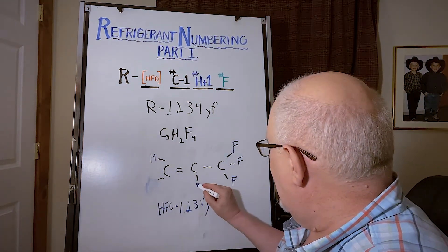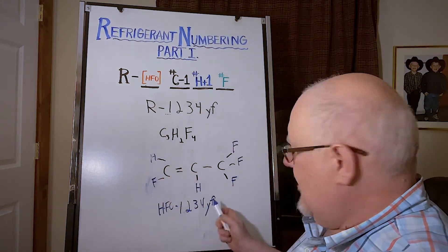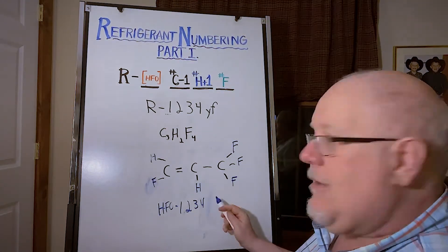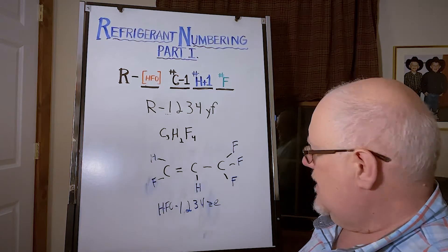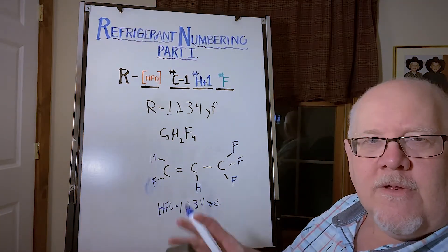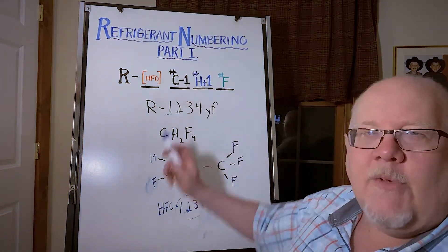So this is 1234yf. If these were switched and we had a hydrogen here and here, then this would become another isomer, 1234ze. You may have heard of 1234ze. Again, smaller case letters out here do the arrangement, these numbers in here off of this formula give you the exact chemical makeup of the refrigerant.